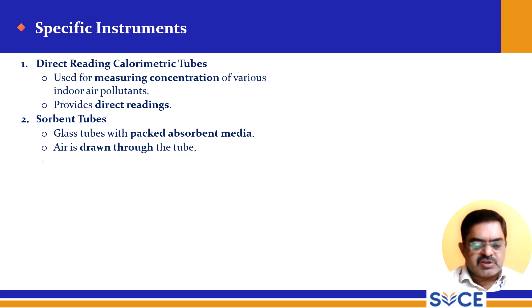So specific instruments: direct reading colorimetric tubes are used for measuring concentration of various indoor air pollutants and provide a direct reading, and sorbent tubes, glass tubes with packed absorbent material or media. Air is drawn through the tube. Airborne pollutants are trapped in the absorbent media, chemically or thermally desorbed, and analyzed thereafter. Now the portable chromatograph, a direct reading instrument for investigating indoor air pollutants, is equipped with standard chemical detectors commonly used in chemical laboratories, and infrared spectrophotometers detect carbon dioxide, carbon monoxide, sulfur hexafluoride, nitrous oxide. They detect even low concentrations above 10 parts per million.